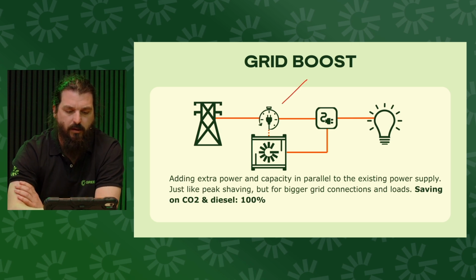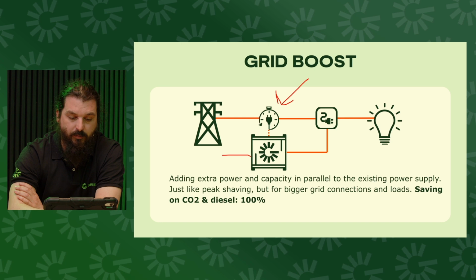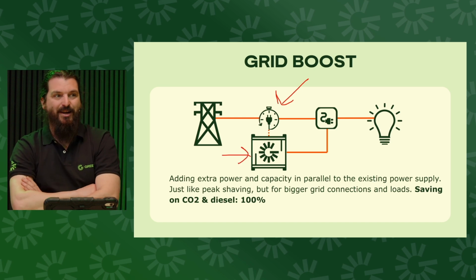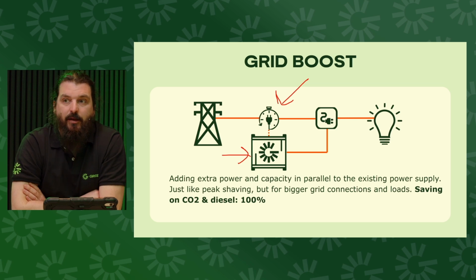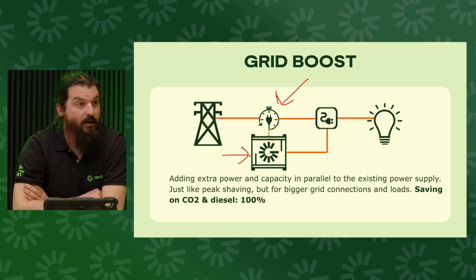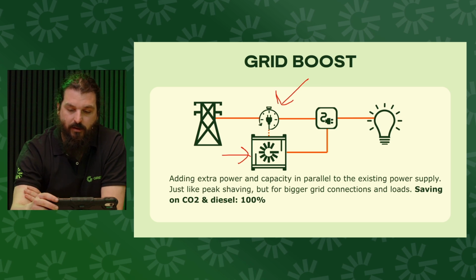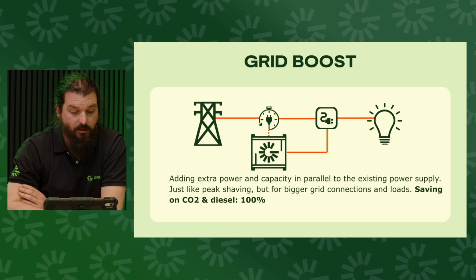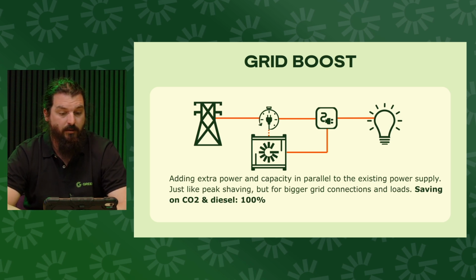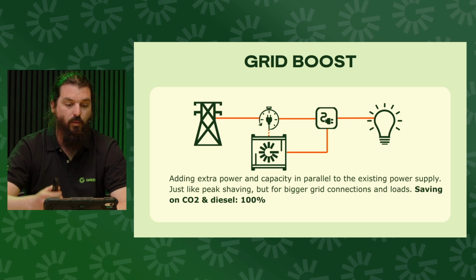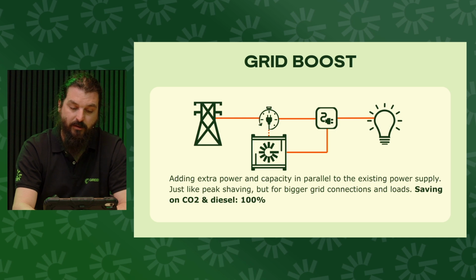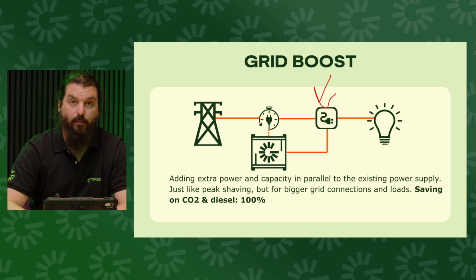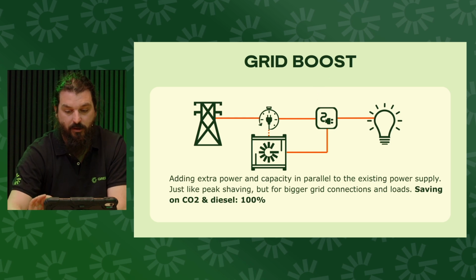So what does that mean? Wherever we place the meter, we tell the EMS in the battery system what the limits are at the point of coupling on the meter, and it will try to keep these limits set. So I have a very nice case to show you guys. Obviously, when we're doing this in parallel, the limit is not one battery anymore. You can use multiple batteries, because the question is not how much capacity the battery system has, but how big your bus is. That's suddenly the limit in the system.